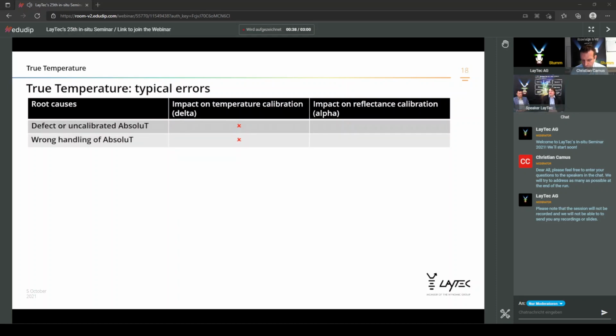So along with the AbsoluT, what we really see from time to time is that the AbsoluT is in perfect order and it's calibrated and working correctly, but still the users achieve a wrong delta value when they do true temperature calibration. And in such cases, it has happened, and it's from time to time happening, that users perform a wrong handling of the AbsoluT.